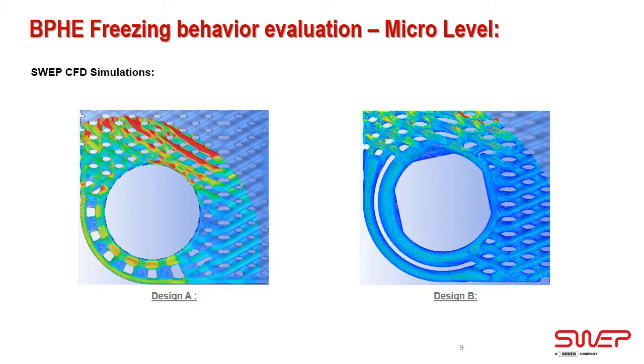If you remember the introduction of the project, the main objectives are to define the BPHE freezing boundary, but also to develop heat exchangers which are more freeze resilient. So how can we improve the freezing resilience? For that, one of our activities is to run CFD simulations of various designs. On this slide you have an example, a comparison between two designs. We are looking around the refrigerant inlet port and at the water channel. What is interesting to evaluate is the homogeneity of the water flow.